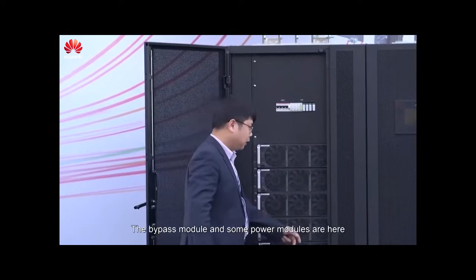These are the small and medium power cabinets. On the left are our 1.2 megawatt and 1.6 megawatt UPS units; we launched the 1.2 megawatt UPS earlier. This is the 1 megawatt cabinet with the highest power density in the industry, with 10 power modules. The bypass module and some power modules are here, with 2 power modules at the bottom. The whole system is 1.2 megawatts, with the bypass module and control module also located here.